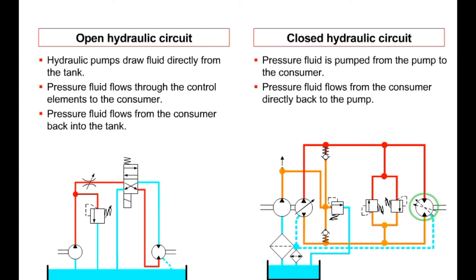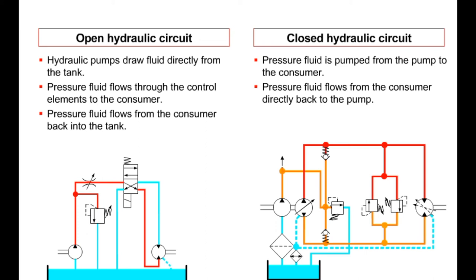In a closed circuit, the return line to the pump is secured by an additional pressure relief valve. The leakage — that is, the flow rate lost from the pump and motor — is fed into a fluid tank and must be fed back into the hydraulic circuit, necessitating an additional but smaller hydraulic pump. Two check valves regulate the in-feed of pressure fluid supplied by the auxiliary pump. An additional pressure valve secures the in-feed circuit. Since leakage fluid cannot adequately cool in a small tank, a cooler must be added in the return line.